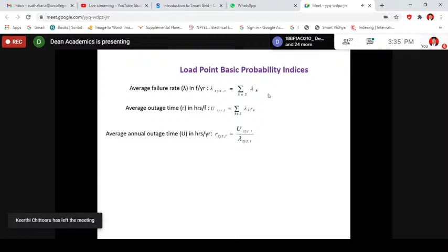The formula appears slightly different because the average or equivalent failure rate equals sigma of lambda I. From a radial distribution point of view, from the input feeder to the load point, all components—bus bars, circuit breaker, transmission line, disconnector, anything relevant to that load point—are considered to be in series, since it is a radial configuration, not a single main configuration. So all elements are treated as being in series.